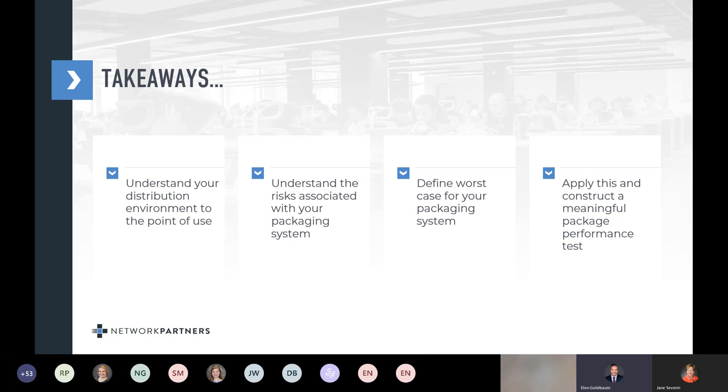So you want to plan these activities up front, with very concise planning for this. As you go through this, it's best practice, I would say, to do 2x EtO for your performance testing, your stability testing, and your device functionality testing. That way, all the data is the same. So if something does happen, you get a short cycle, or the sterilizer fails for whatever reason, which does happen from time to time, you know your product's qualified for one more run through it. Okay, great. Thanks for expanding on that.